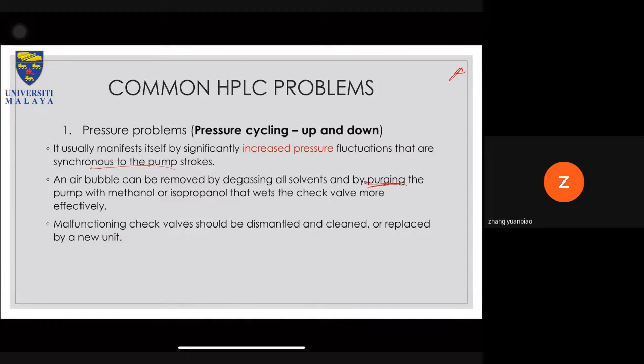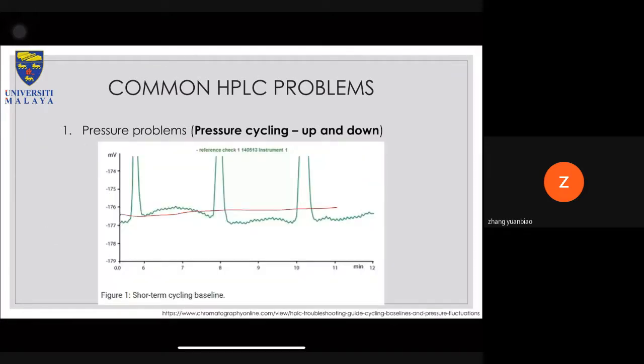All right, so this is an example of pressure cycling going up and down. As you can see here, for a normal run, it will just go flat. But if it's cycling, it goes up very, very high during the piston stroke, and then during the dampening effect, it will go something like this. So you can see that it's still going up and down, and then pump stroke again, and then dampener, pump stroke again, dampener. By looking at the pressure, you can actually know if there is any issue caused particularly by the pump.